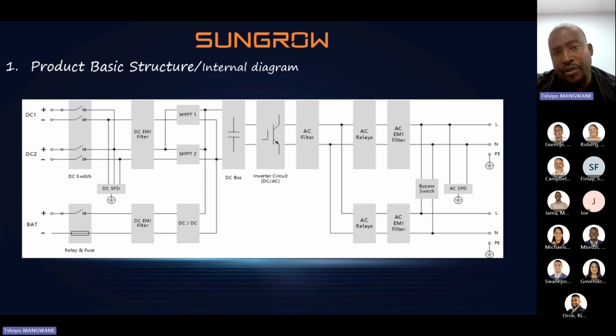In this scenario, you'll find that the customer doesn't have money for the batteries. He only wants the inverter and the PV in the meantime. So if the grid connects, it will act like a grid tie system and supply to the load as well. Should the grid fail in the event of load shedding, the system will continue working and supplying power to the building through the PV modules.